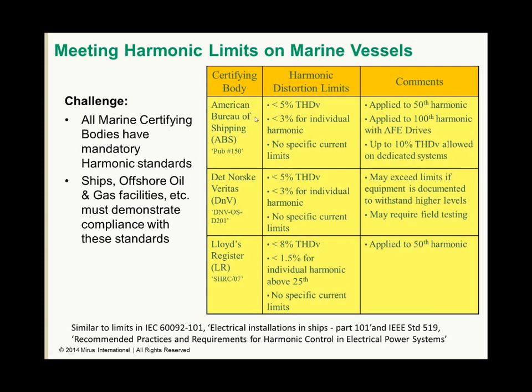This table shows just some examples of some of the certifying bodies and the requirements of harmonic limits. Most of them are targeting the voltage distortion, total harmonic voltage distortion, and individual harmonic voltage distortions.